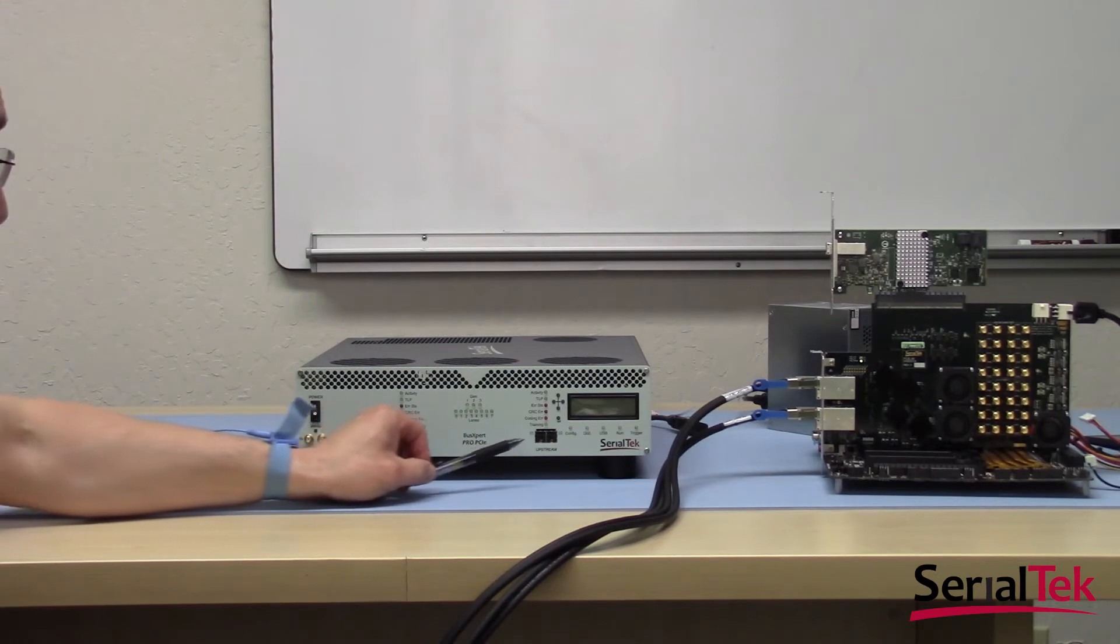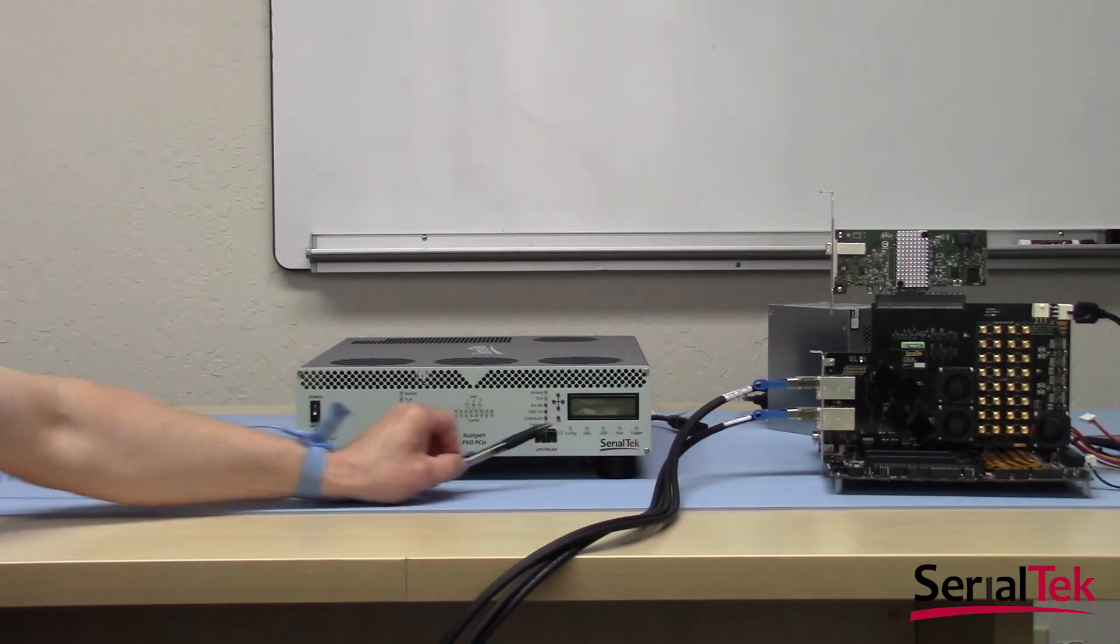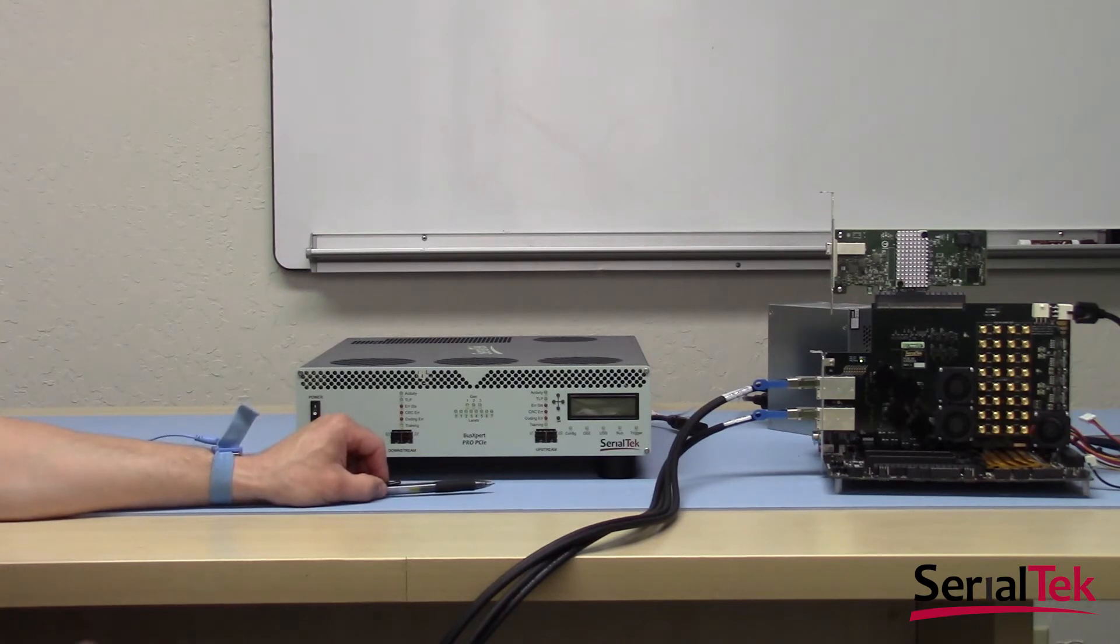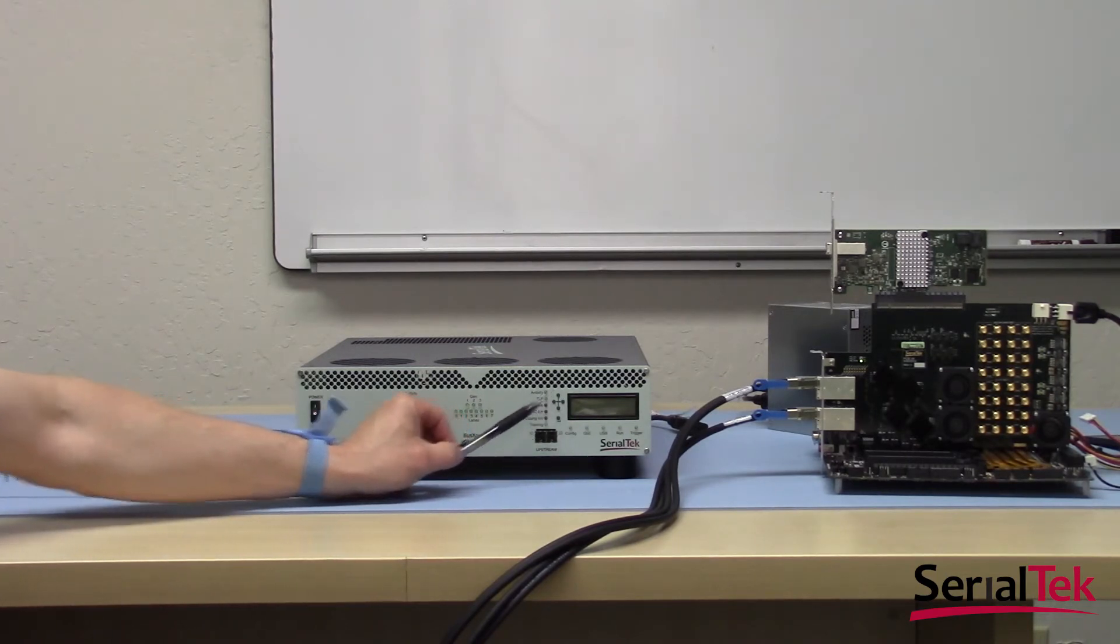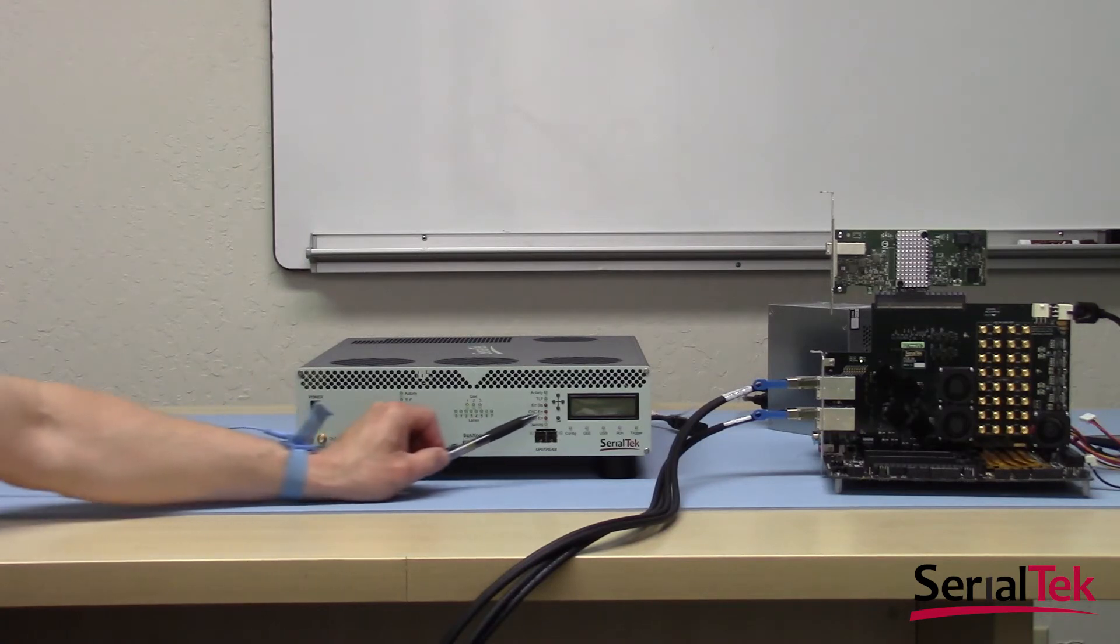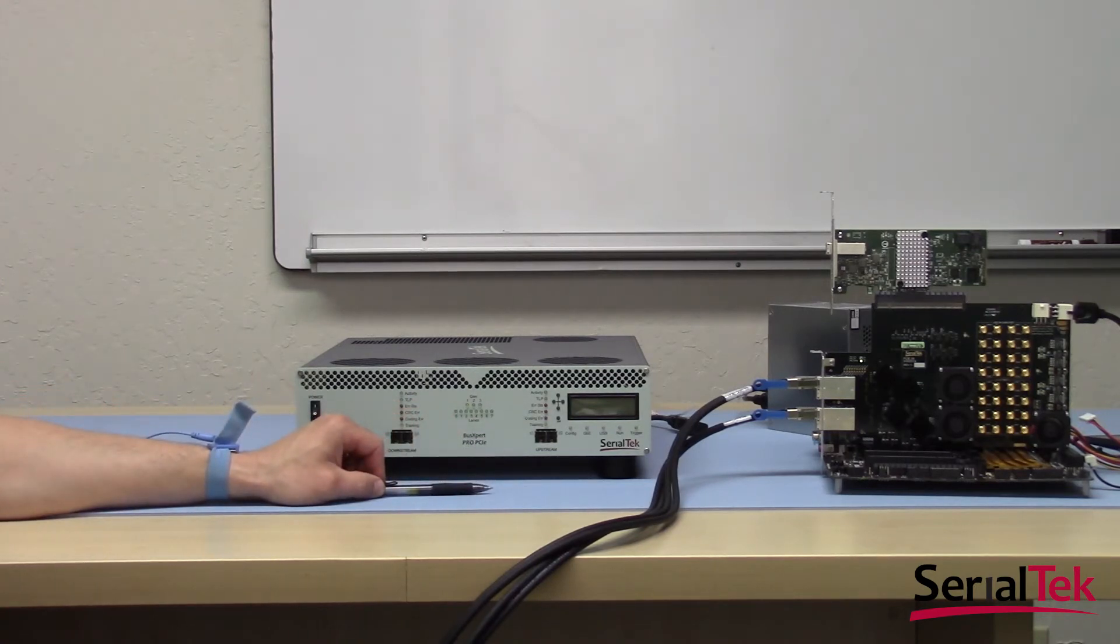Let's see. Here on the right side, we have an LCD display, which shows the analyzer serial number, IP address, and unit number. The unit number comes in handy when you're trying to distinguish which analyzer is which in a situation where multiple analyzers are daisy-chained together, what we refer to as cascading. Here, just to the left of the LCD display, we have a set of buttons that can be used to modify the IP address, even without a software connection to the analyzer. So directly here through the front panel, we can modify the IP address.